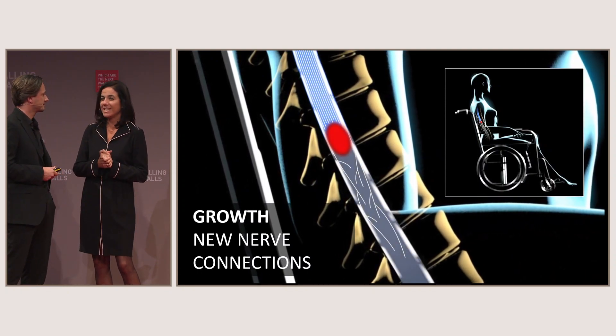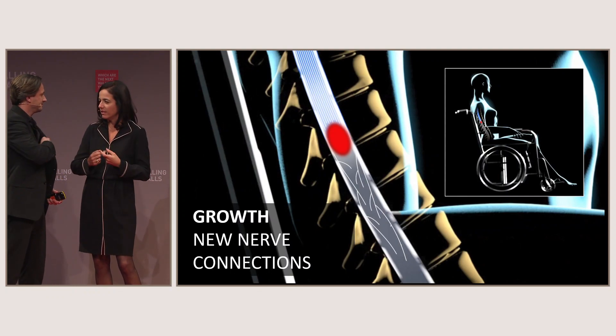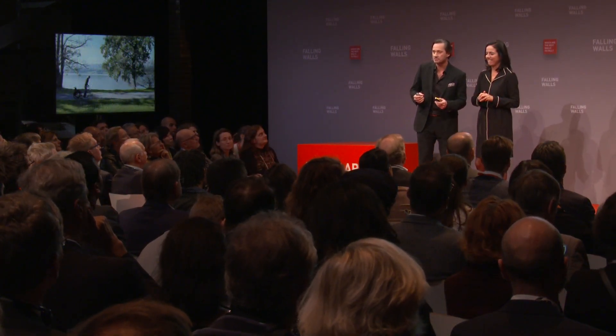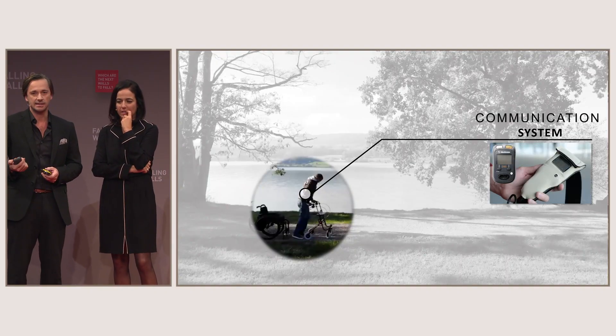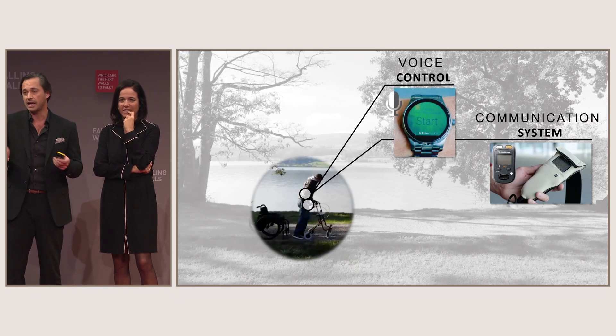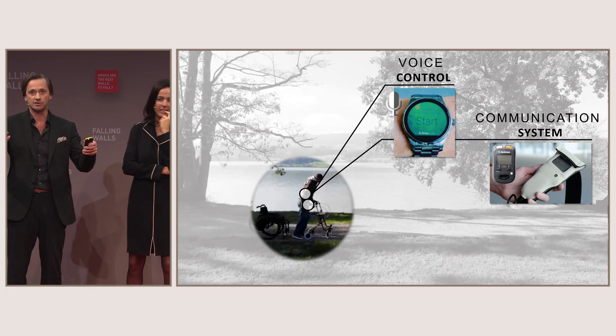After six months of training, David was still improving, and it was hard to stop the study. He wanted to keep using the device outside the laboratory. So the engineers built a proof-of-concept system: a small patient programmer to control the stimulation, activatable with a remote control or even a watch that responds to his voice, delivering complex spatio-temporal stimulation patterns to enable walking in real-world settings.